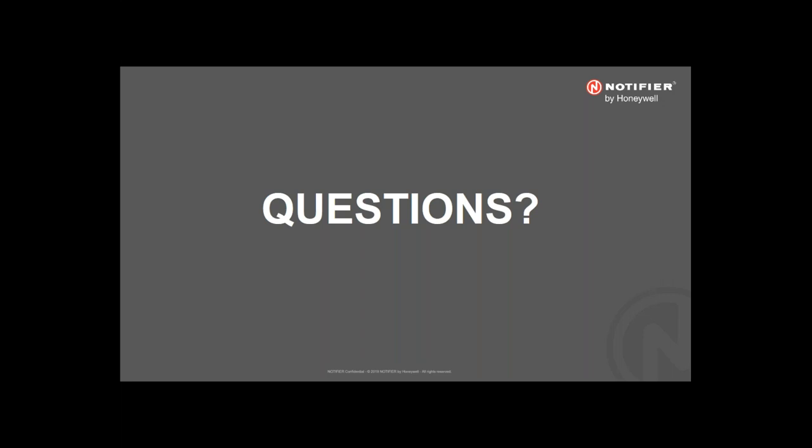Okay, thank you. And just one more on a specific type of facility. In a school building or daycare, so for younger children, are naps considered sleeping? Would a facility manager need to follow those sleeping room guidelines for a daycare? I suppose that could also be a preschool setting. And as a follow-up, I'm wondering if they're referring to the low-frequency sounders or to CO detection. Yes, low-frequency, specifically here. So it wouldn't be required for those. They wouldn't be considered sleeping spaces because there would be active adults there monitoring situations, similar to a hospital. Hospitals have patients in their sleeping rooms as well, but the low frequency sounders are not required because there are people there to monitor the system and the applications.